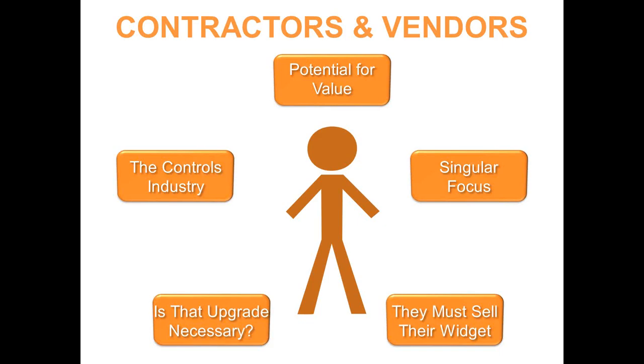And it's sad for us to see that in most cases when controls vendors come in under a contract that essentially is only hours per month, the building engineer, because of their background and their lack of understanding of how buildings actually should operate, essentially leaves it up to the controls contractor to provide the services and design what those services are. So in many cases it's about addressing alarm issues, it's about looking at particular problems of sensors that might have failed, rather than calibration, resequencing, rescheduling, redoing or repairing reset schedules, and doing some of the things that actually do provide performance in the building.